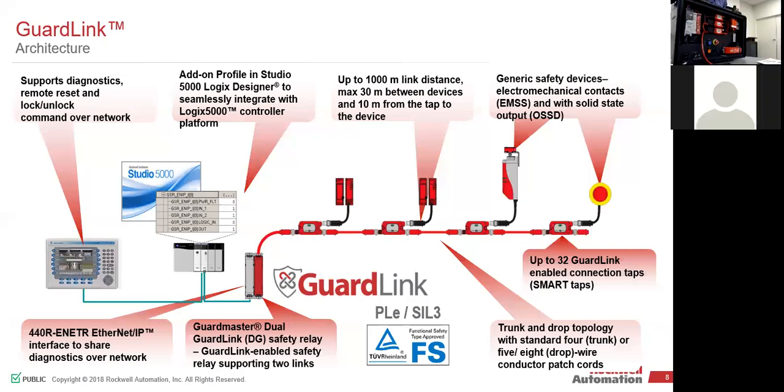Now if I switch on the e-stop, if you notice over here, the top and the bottom are still blinking green, right? And the one in the middle goes red, it still keeps the trunk alive, meaning all of these devices are still operating, and you know exactly where this e-stop was pressed, because all you're now looking for is this red. And this red node, or this tap, is one node, right? This node can then be identified on your HMI, where you can alias it, or you can write some descriptive comment saying it's zone 2, level 1, or whatever. So that helps you to identify that problem much easier. So you can also time it. If you actually know John is pressing that, you can just time it, and you can make sure that that's not happening.